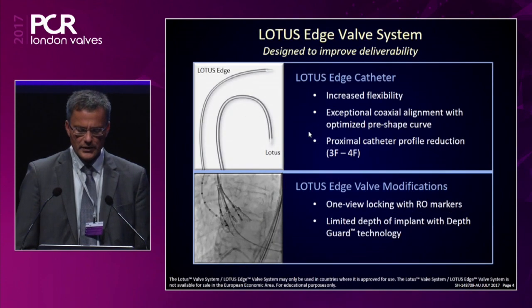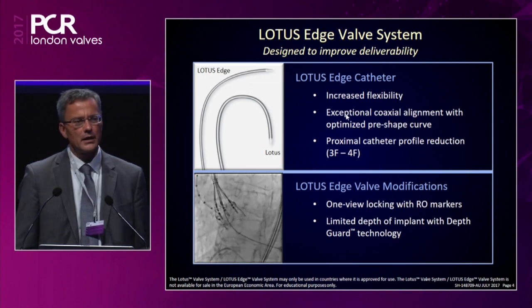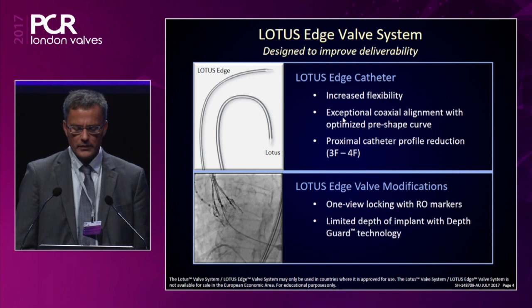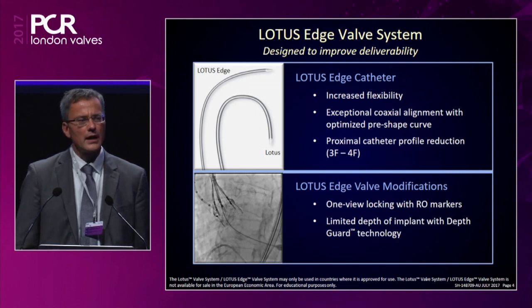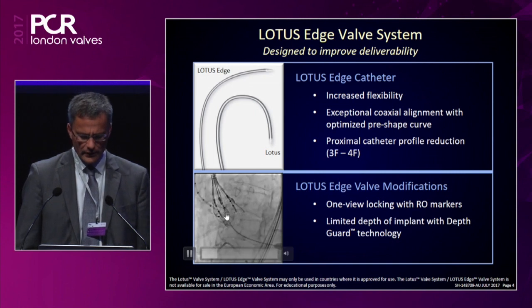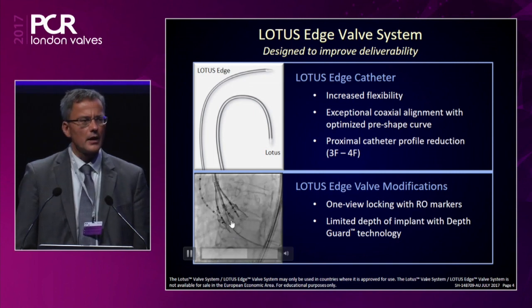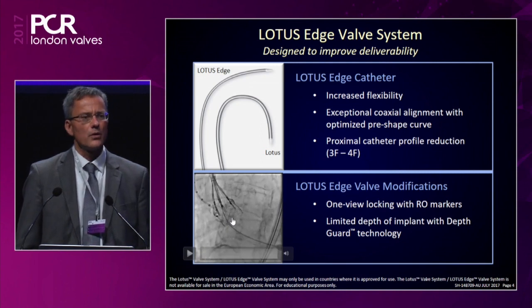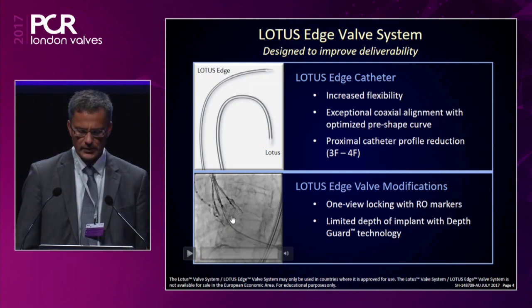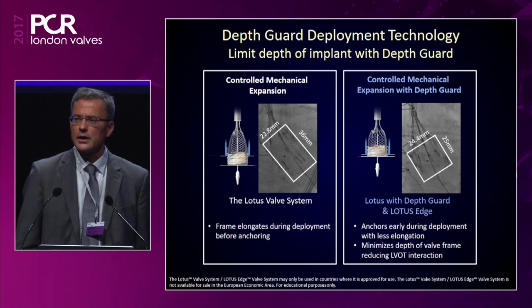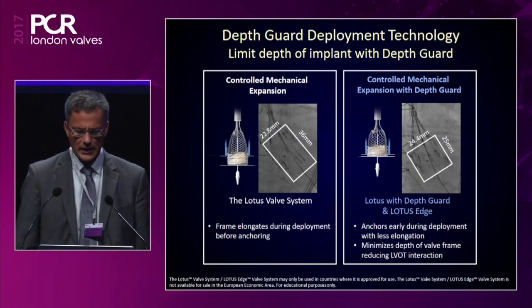Here you see that the catheter is more flexible, so we have a better coaxial alignment with an optimized pre-shape curve, and the profile is smaller, 3 to 4 French, as compared to the classical LOTUS system. You see here that there are radiopaque markers, and with the radiopaque markers, you just need one view to be sure that the valve is completely locked. And in addition, the LOTUS Edge comes with a depth guard, and the depth guard is important because with that we can better control the position of the LOTUS valve in the LVOT.